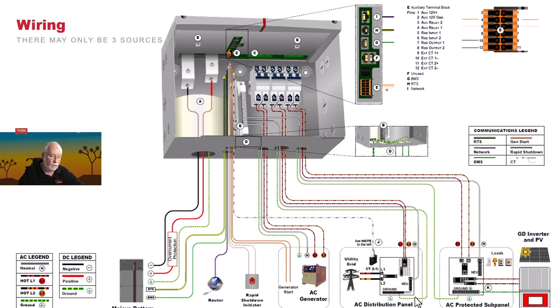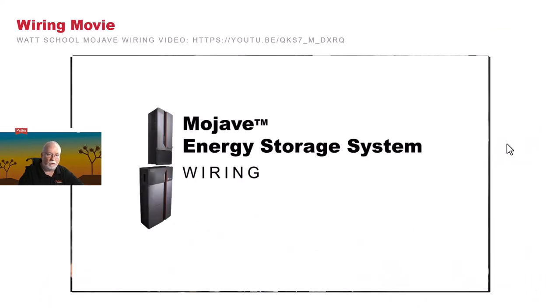There is a neutral ground bond shown here in the diagram. Again, this is the single neutral ground bond. There is none at the generator. There is none at the backup loads panel. As we move across, again, there's your backup loads panel and your back-fed solar inverter. So it's really simple. This is right out of the planning guide. So very simple to use.